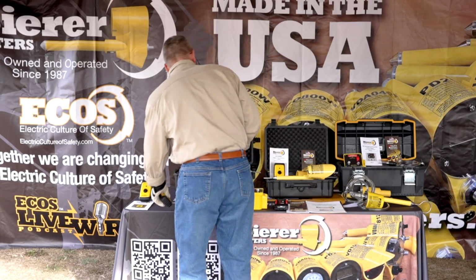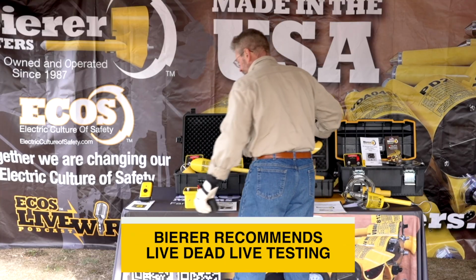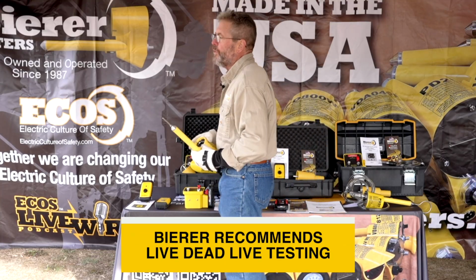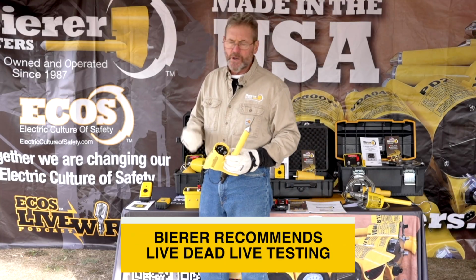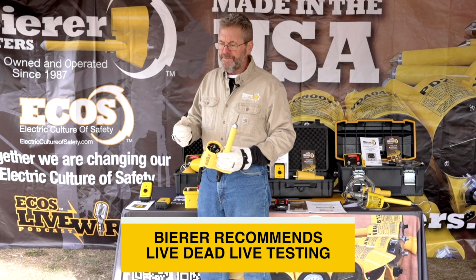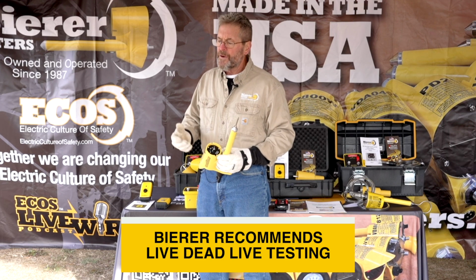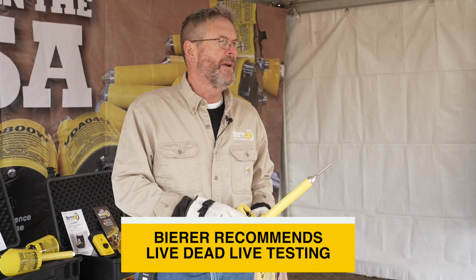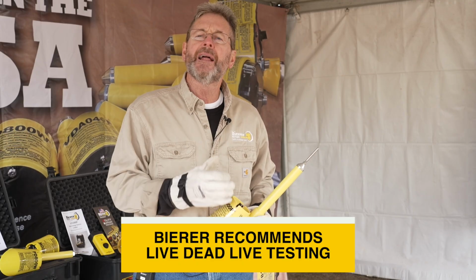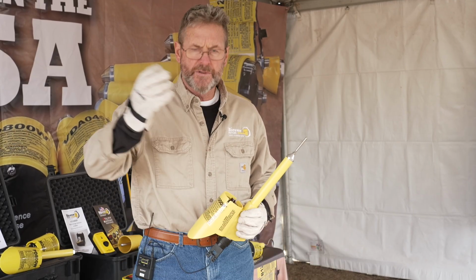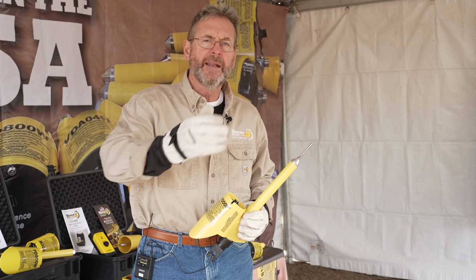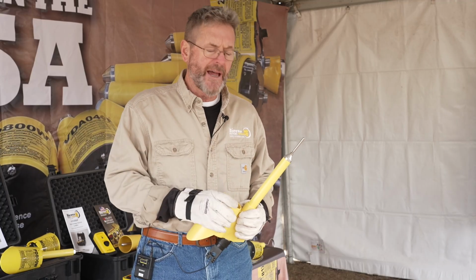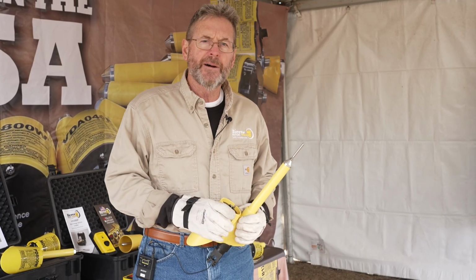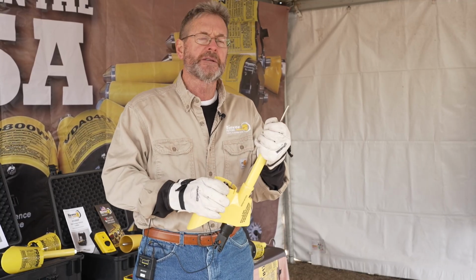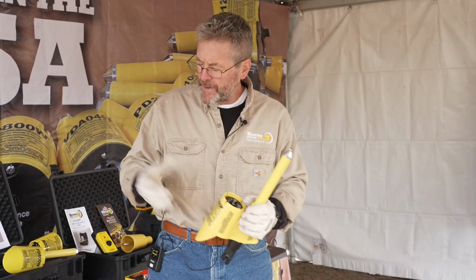So what we're going to do is use a single point device and perform our live dead live test. If you're out in the field—let's say a storm restoration, an outage—and you don't have a live known voltage source to perform a live dead live test, the handheld power supply on your single point device is perfect, because you bring it with you.